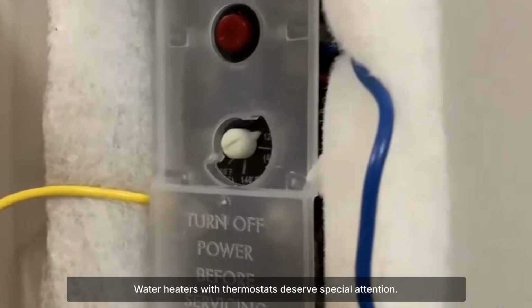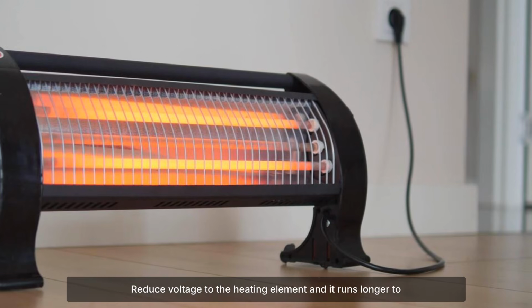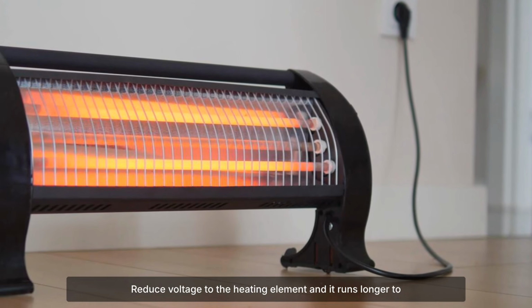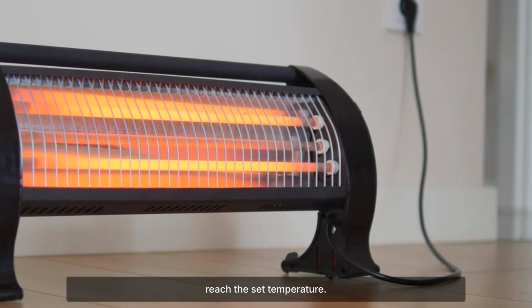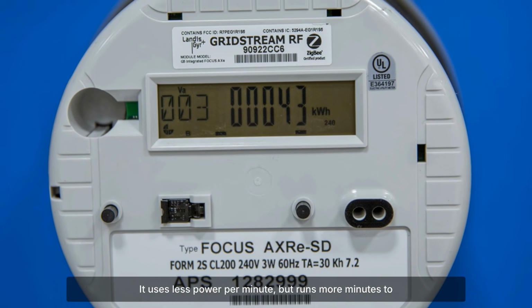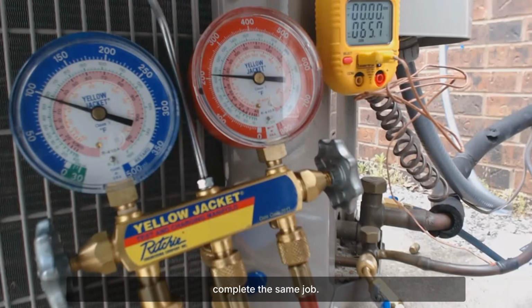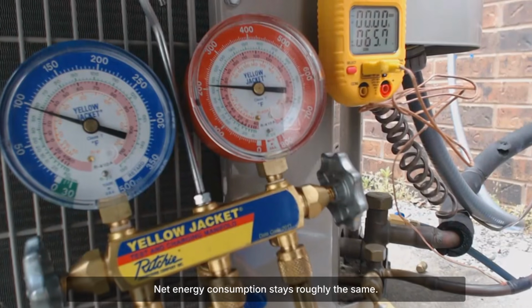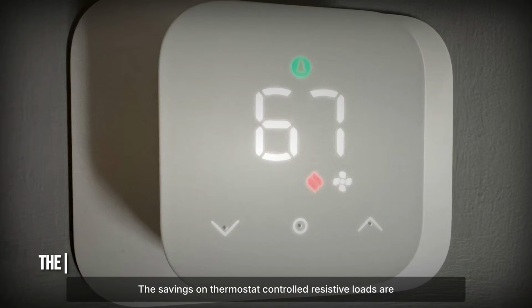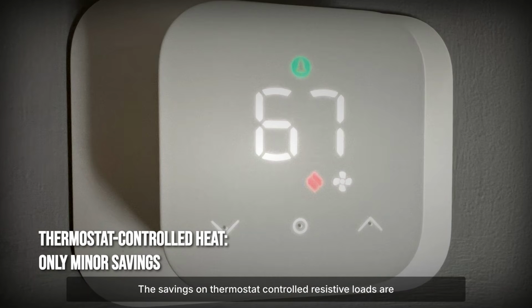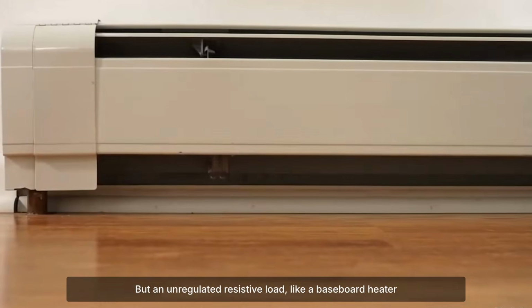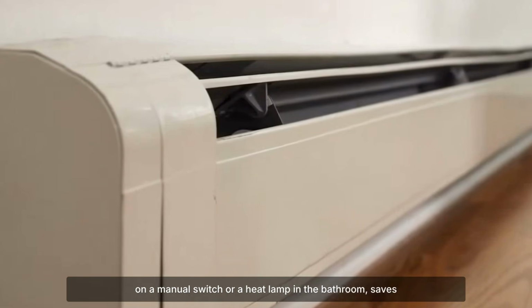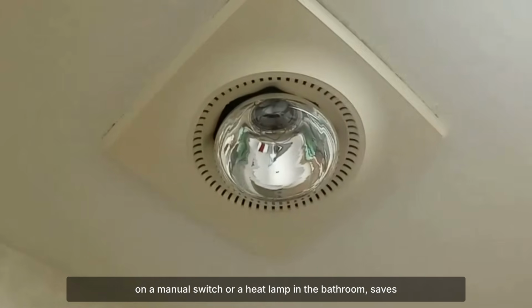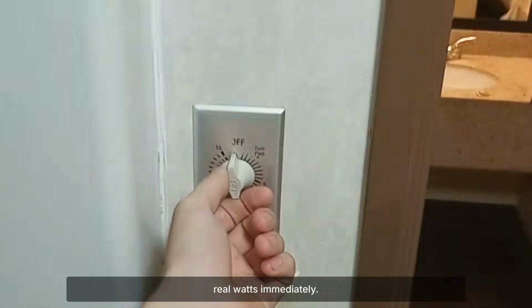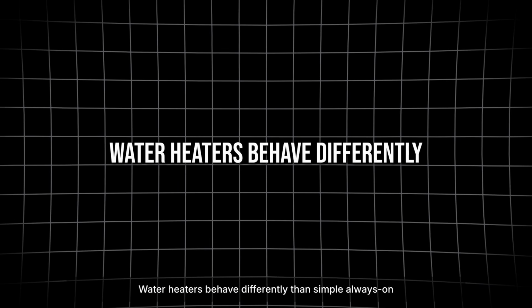Water heaters with thermostats deserve special attention. Reduce voltage to the heating element and it runs longer to reach the set temperature. It uses less power per minute but runs more minutes to complete the same job. Net energy consumption stays roughly the same. The savings on thermostat-controlled resistive loads are minimal, but an unregulated resistive load, like a baseboard heater on a manual switch or a heat lamp in the bathroom, saves real watts immediately. Water heaters behave differently than simple always-on resistive loads.